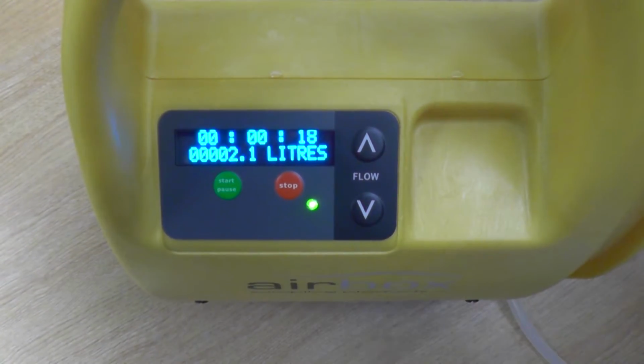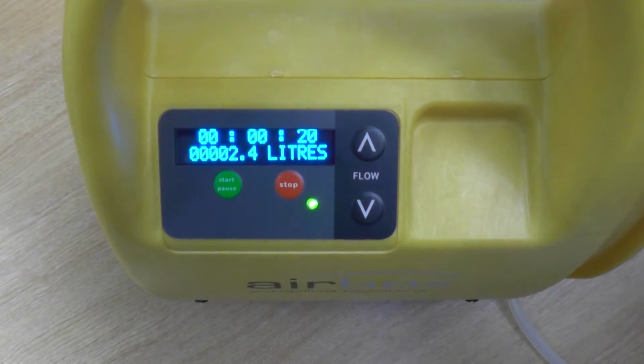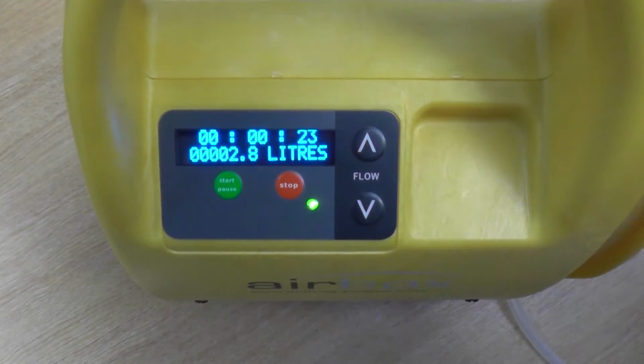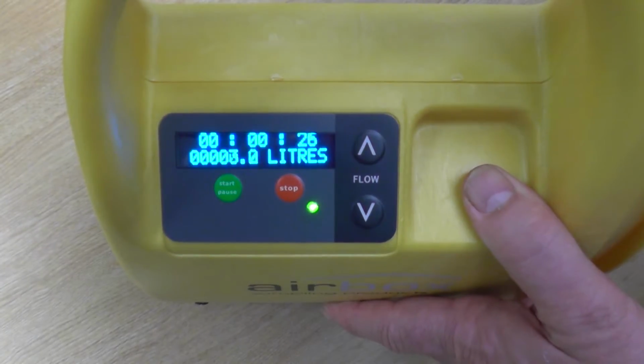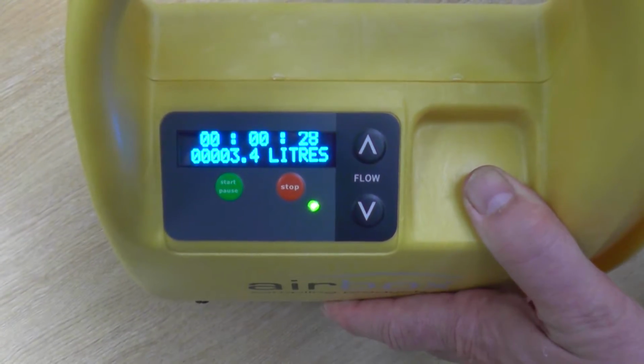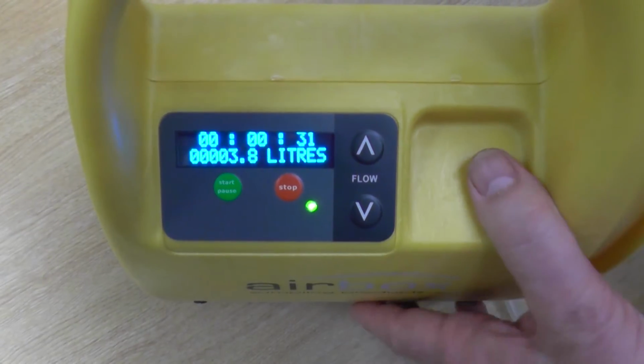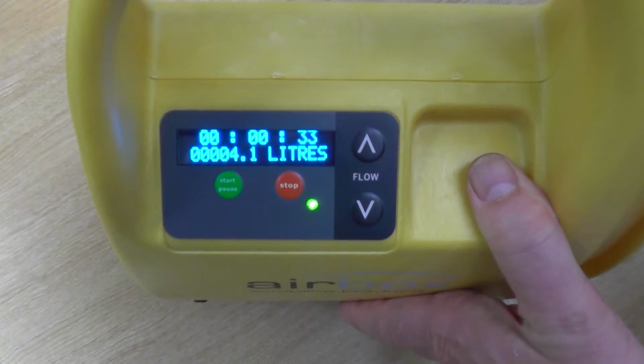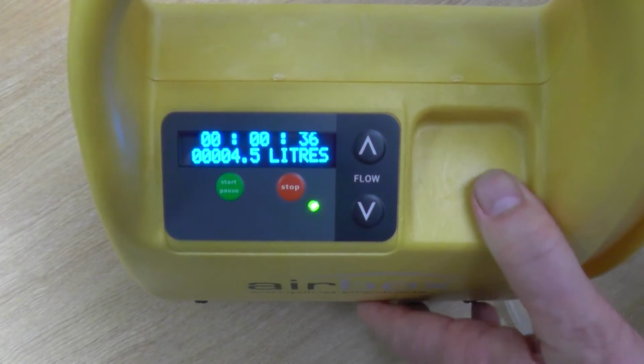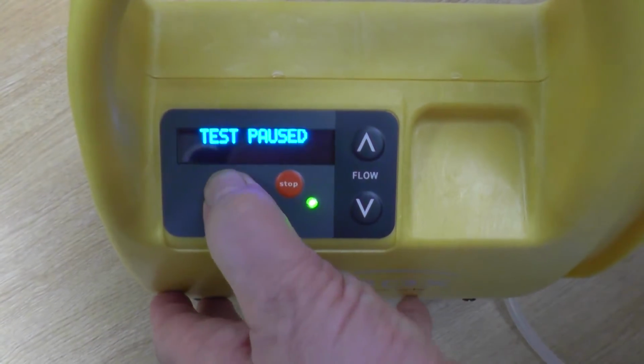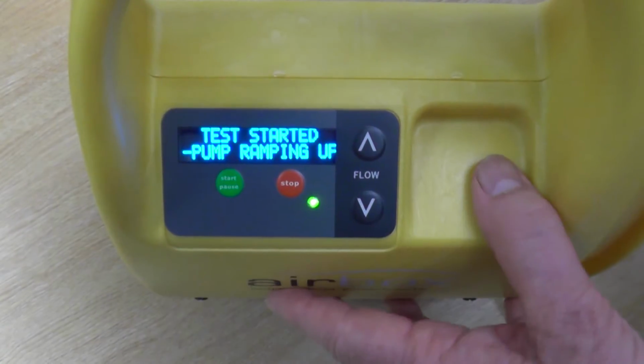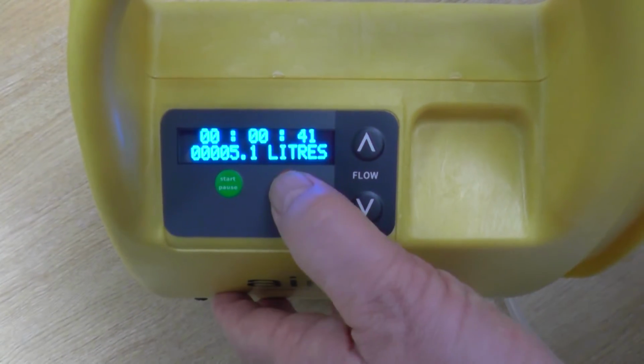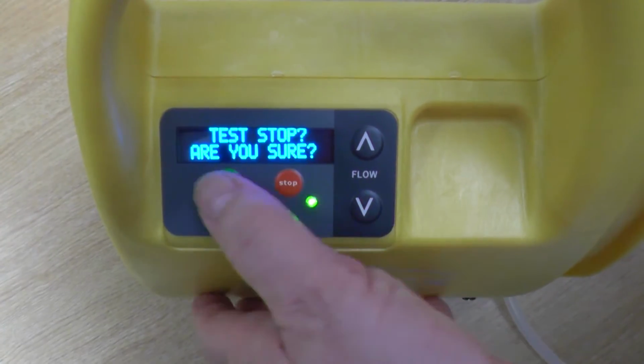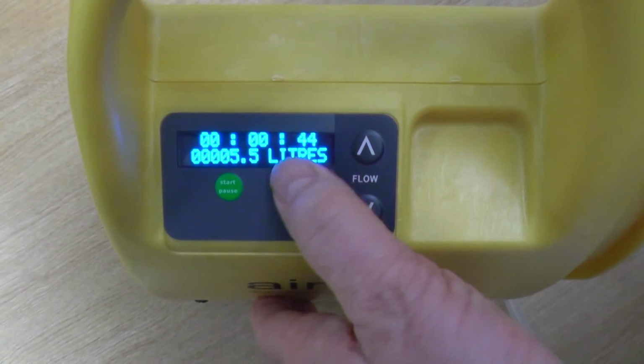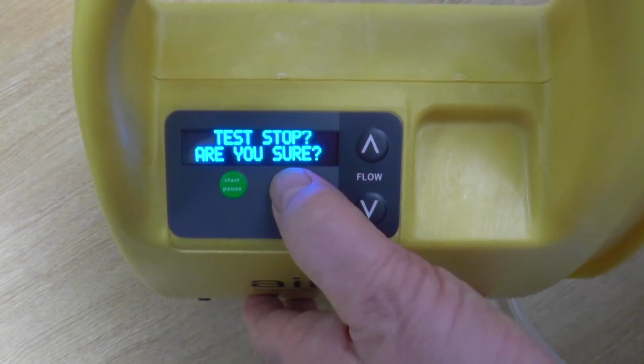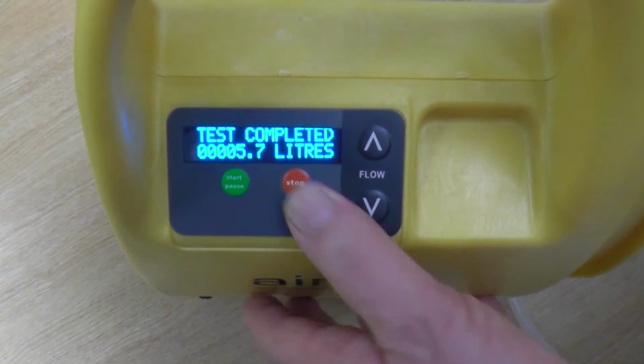It'll then run on a little bit longer to make sure that you have collected all of the air that you originally asked for. So the calculation will be 60 minutes at 8 litres, 480. So even if it's run an hour, it'll continue to run for a few more seconds until it knows it's actually collected the 480 litres you want. Again, you can pause. If you restart it, it'll start where it left off. If you press stop by mistake, again, you can restart it. I'm going to stop it and show you how to do a capacity test.